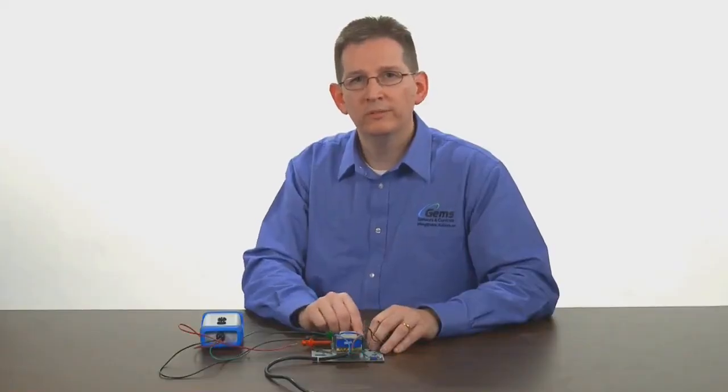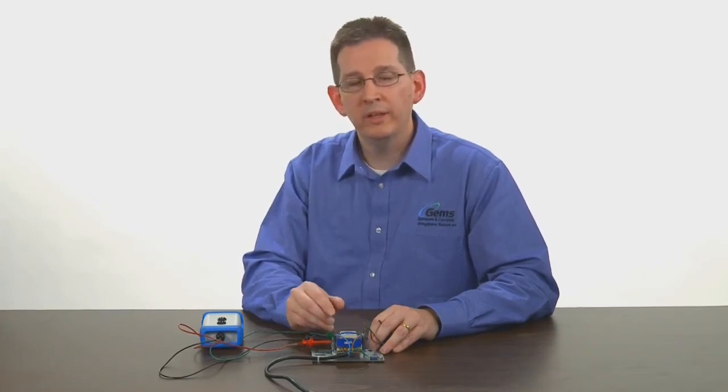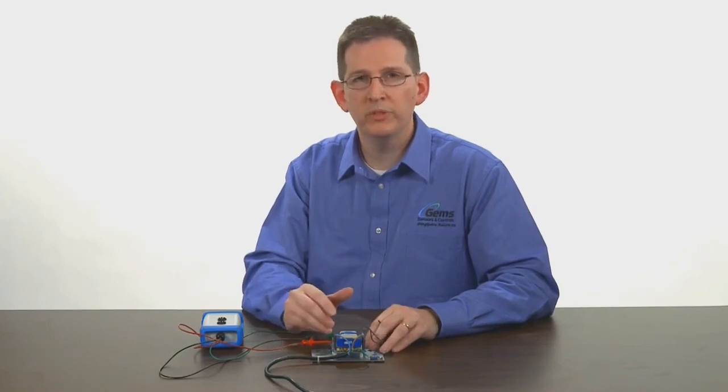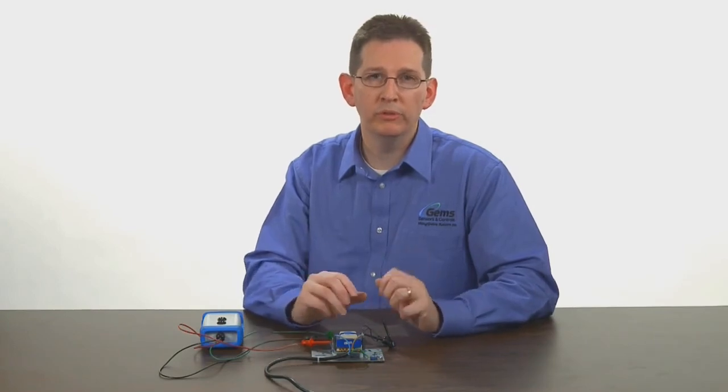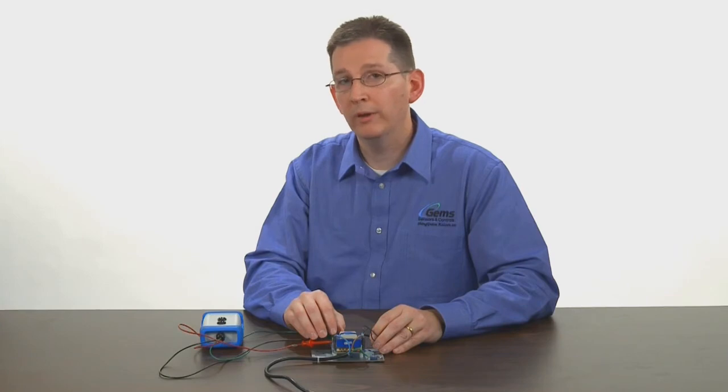Once you've checked your relay for proper functionality, a few other things to consider. The cleanliness of your probes, is there any buildup of material on those causing a case called bridging, material between two probes or to the reference point. Also, verify that you've wired your probes correctly, and that you have nice tight seals and continuity in your wiring.